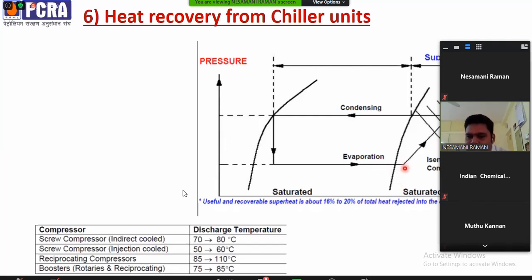The refrigerant vapor enters the compressor, and during compression heat is added, so its pressure as well as temperature increases. The refrigerant reaches the superheated level. The superheated refrigerant that comes out of the compressor enters the condenser for cooling. The phase change occurs here, and high pressure vapor becomes high pressure liquid after the condenser. So here is a chance for heat recovery: this high superheat is not necessary for the condenser, so we install a desuperheater in the chillers. It will recover the superheat so that the temperature comes down while entering the condenser.